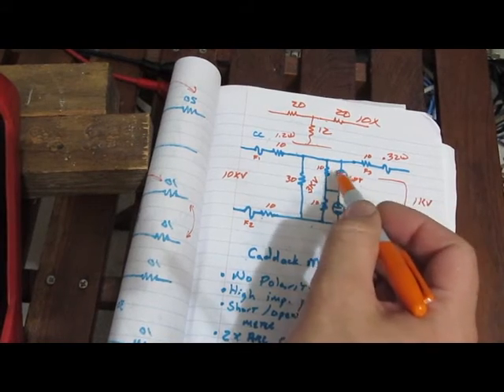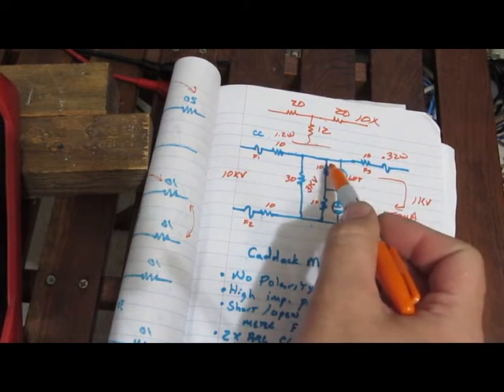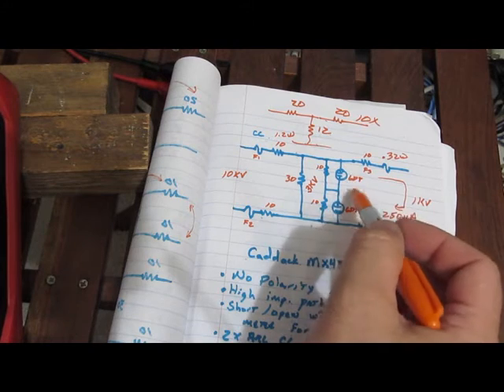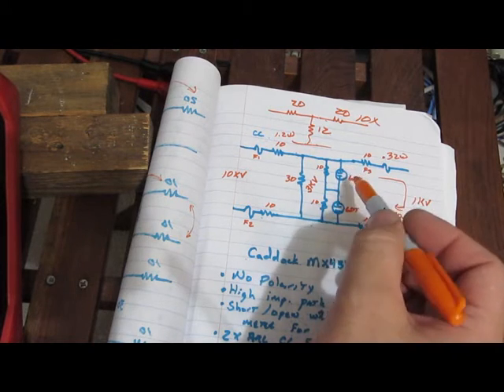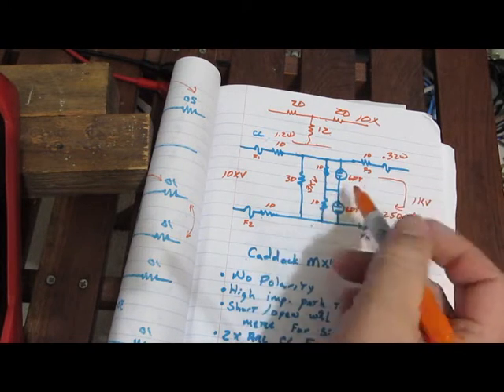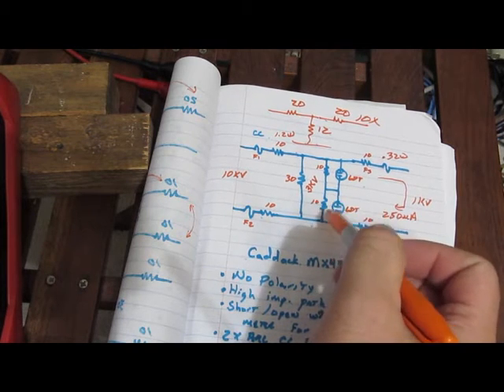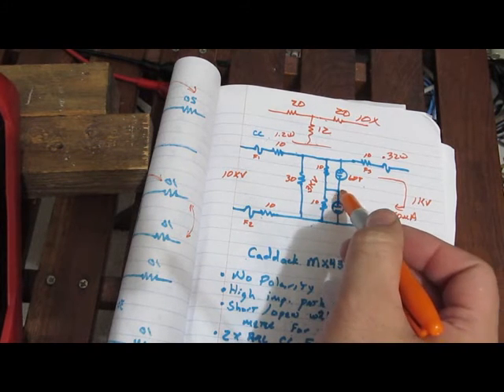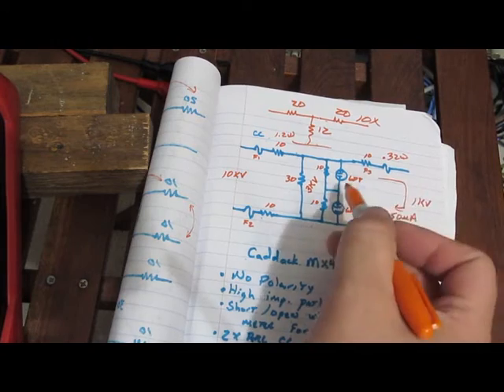The reason I've separated out the 2 10s is this resistance causes these gas discharge tubes, which are in series, to actually charge at the same rate. So when one fires due to a transient, they share the voltage across them and kick at roughly the same point.